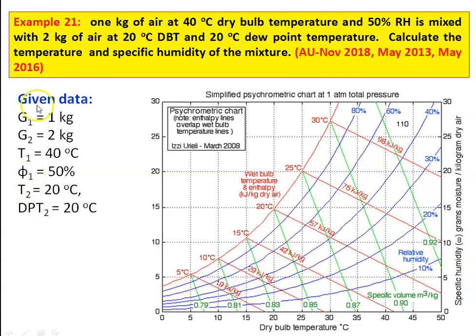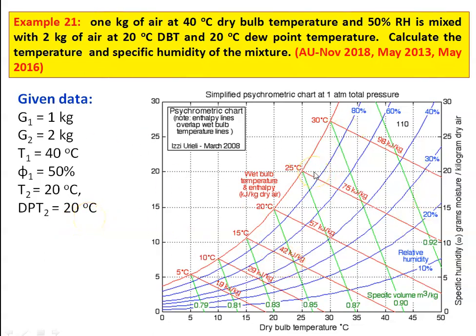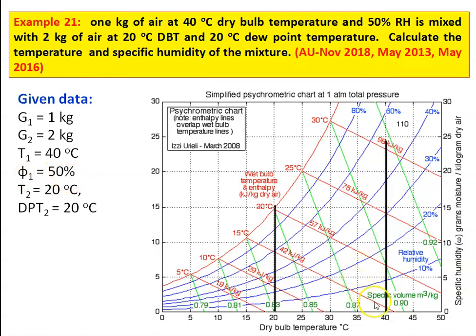The given data: G1, mass of air in the first duct, is 1 kg; G2, mass of air in the second duct, is 2 kg. Inlet condition: T1 = 40°C and φ1 = 50% relative humidity. For the second pipe: T2 = 20°C and dew point temperature is also 20°C. Now, using the psychrometric chart, we solve the problem. We fix the initial condition — T1 = 40°C and φ1 = 50%, this is point 1. The second condition T2 = 20°C dry bulb temperature and dew point temperature 20°C — this is point number 2.